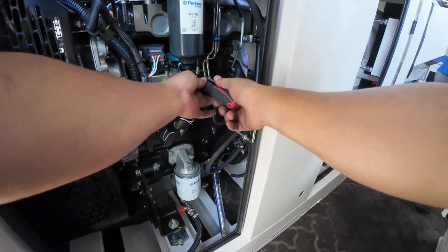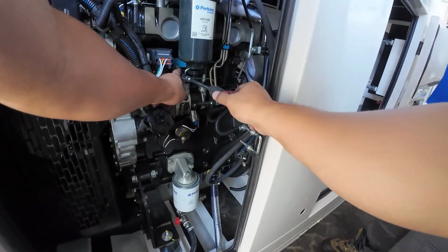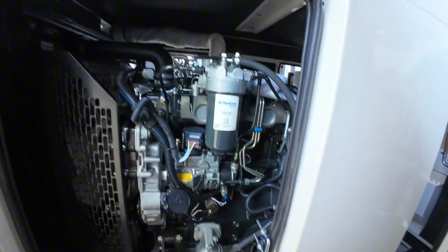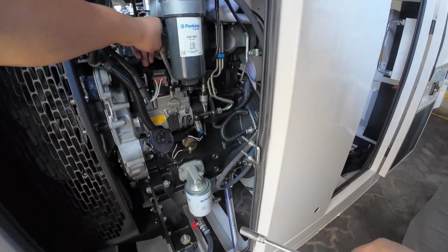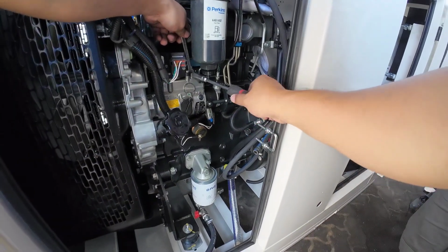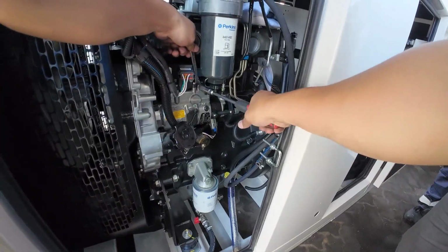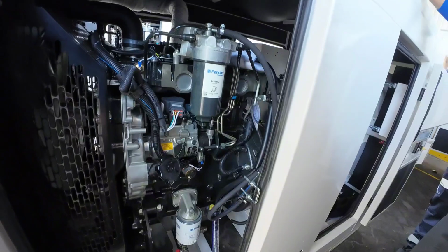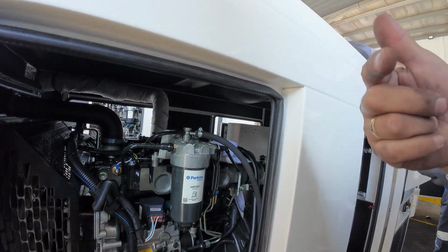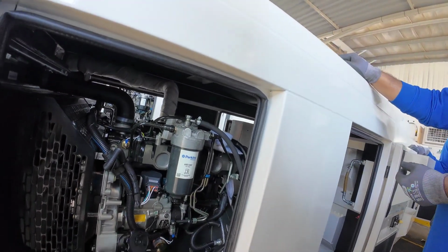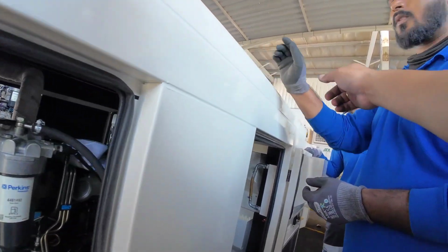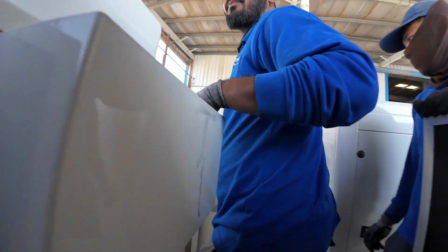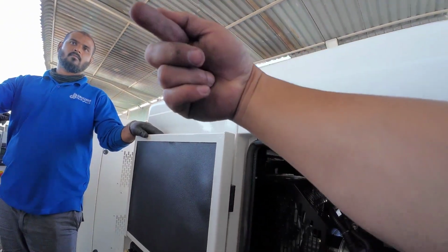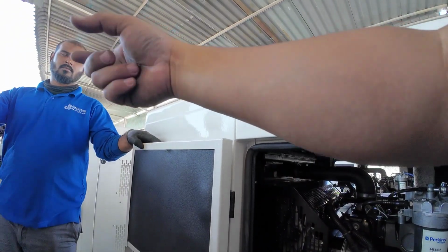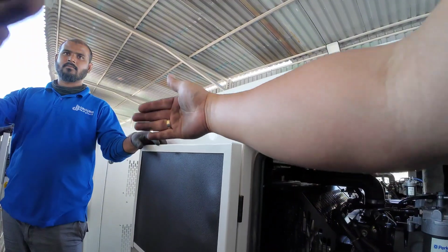After that we need to check if it's working correctly. That's why we're here in our testing and commissioning area, so we need to assure it is working properly and ready for our load tests and ready for our customer. If we deliver this generator, they can use it at the proper load they wanted. But you must know how to do these things, and you must understand and study how it will work while doing this adjustment.